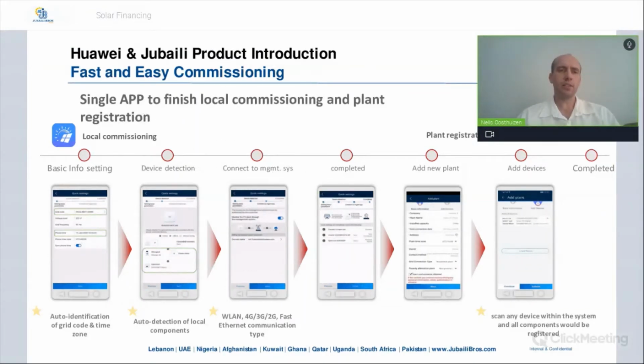Then moving over, this is the fast and easy commissioning. Huawei inverters allow for easy on-site commissioning via your cell phone. There's also a second option to commission via a web interface if you've got a smart logger. The commissioning process is very easy: from basic info, automatic device detection, to setting up your management system, indicating if you're using WLAN, 4G, 3G, fast Ethernet, whatever your internet connection is. That's easy to set up. Once those first 3 steps are done, your system is basically complete. From there, you can add more plants or more devices as you expand, and everything is as easy as doing it on your phone on site, or you could also do it remotely.